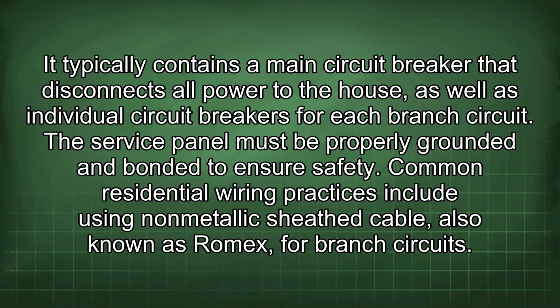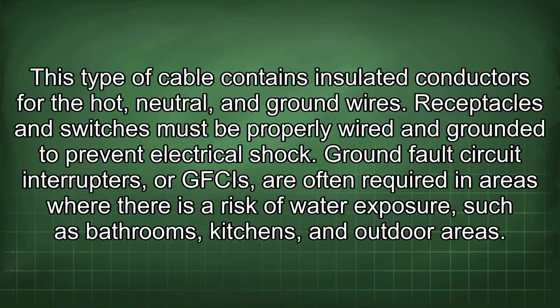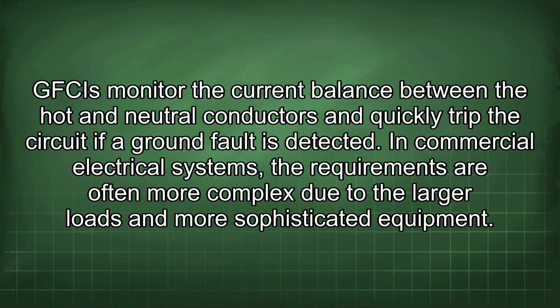Common residential wiring practices include using non-metallic sheathed cable, also known as Romex, for branch circuits. This type of cable contains insulated conductors for the hot, neutral, and ground wires. Receptacles and switches must be properly wired and grounded to prevent electrical shock. Ground fault circuit interrupters, or GFCIs, are often required in areas where there is a risk of water exposure, such as bathrooms, kitchens, and outdoor areas.